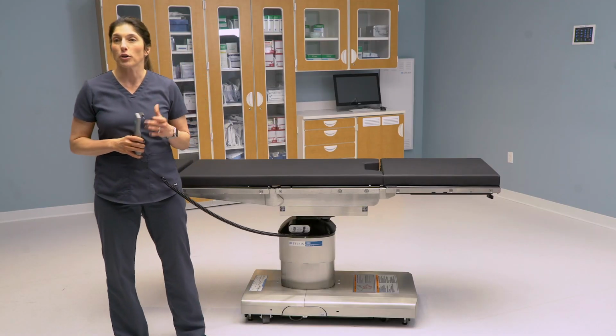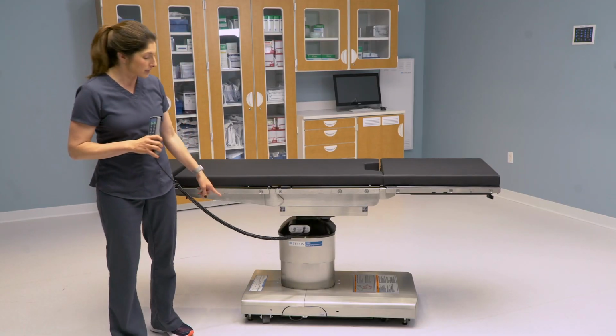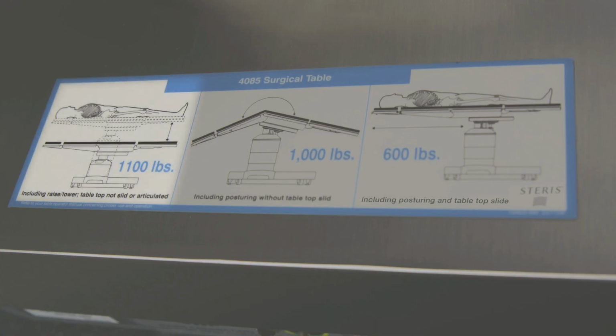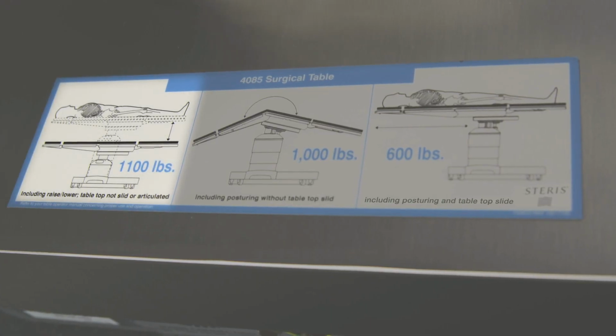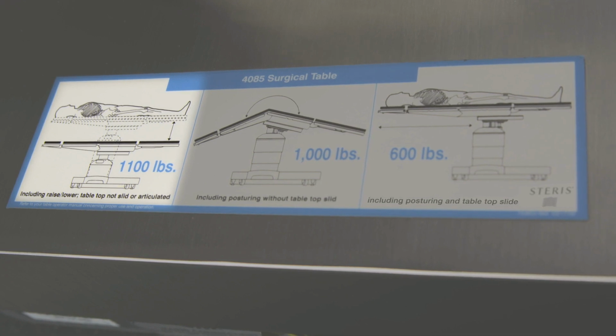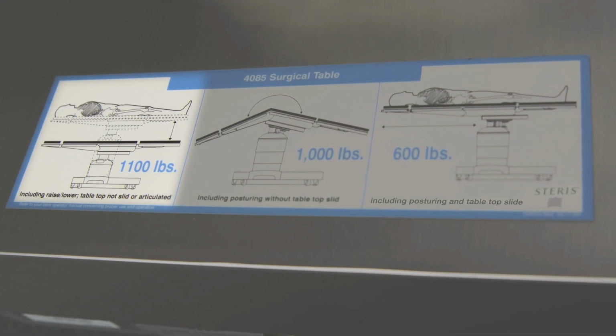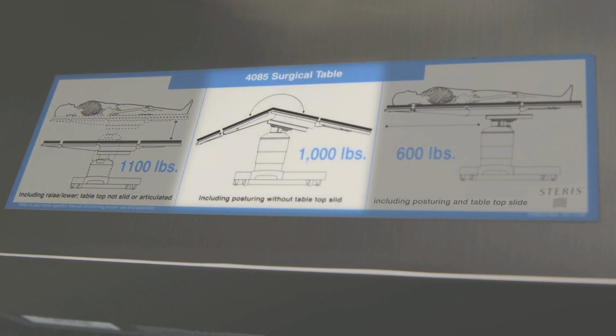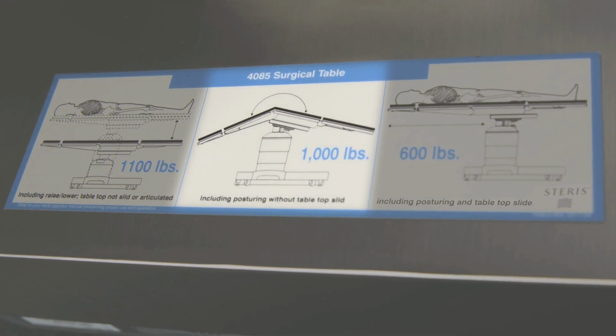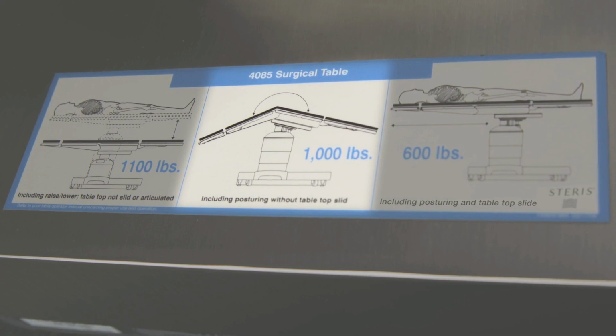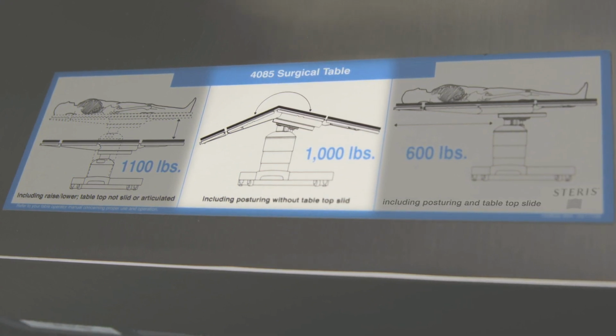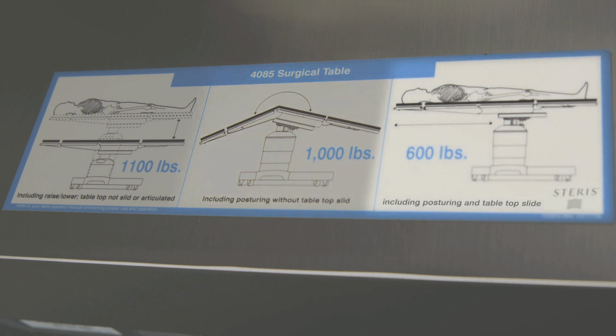So when we talk about weight claims, there are three weight claims that you should be aware of, all three listed on this label below. The first one is the tabletop centered over the column, height up and down only, and that's 1,100 pounds. The primary one is 1,000 pounds, and that's the tabletop centered over the column with full articulations. You can do steep T-bird, you can do left and right tilt, you can do up and down, you can do any of the articulations and hold up to 1,000 pounds when the tabletop is centered over the column. Now, when you slide the tabletop to the head or to the foot, whether it be 1 inch or 9 inches, your weight capacity goes to 600 pounds.